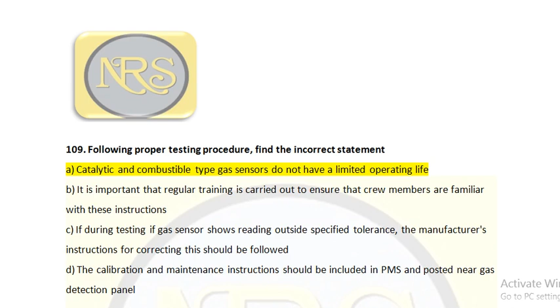The correct answer is option A: catalytic and combustible type gas sensors do not have a limited operating life. This is an incorrect statement, so it is the answer for question 109. Combustible gas sensors use filaments, and catalytic sensors use a catalytic compound; these have a life period, they have an expiry date, so it's not lifelong usage. They do have a limited operating life, that's why we calibrate, treat, and change them as part of maintenance. For question 109, option A is the correct answer.